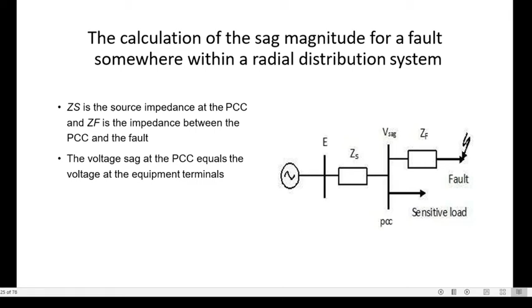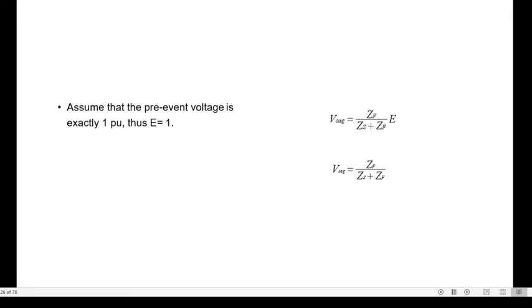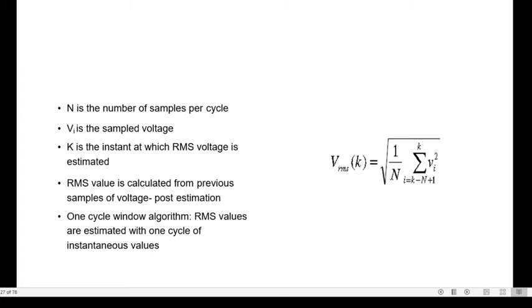So this is the simple calculation, just go through this, that will give you the voltage sag magnitude as ZF upon ZS plus ZF into the EMF E. Assume that the pre-event voltage is exactly 1 per unit, so we can put E equal to 1. This is the expression with the help of which one can find out the voltage sag RMS value for a number of events.